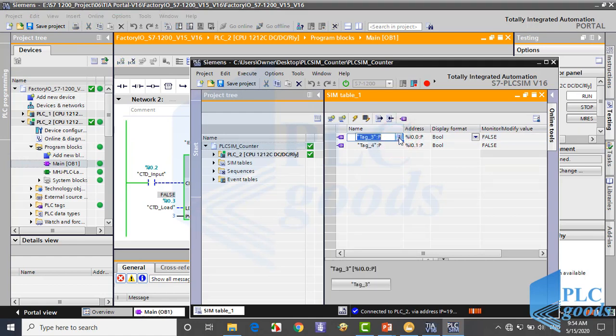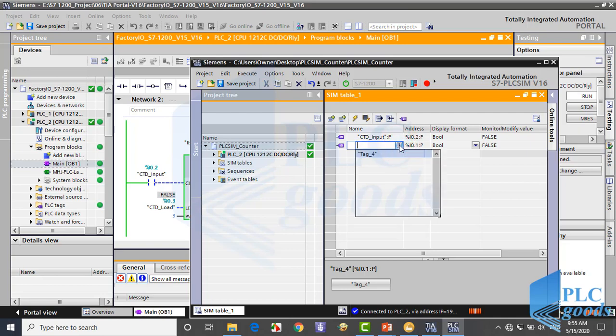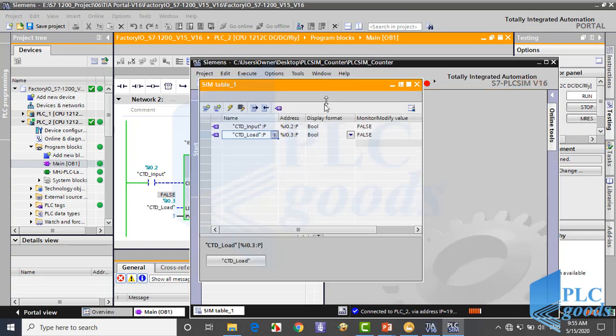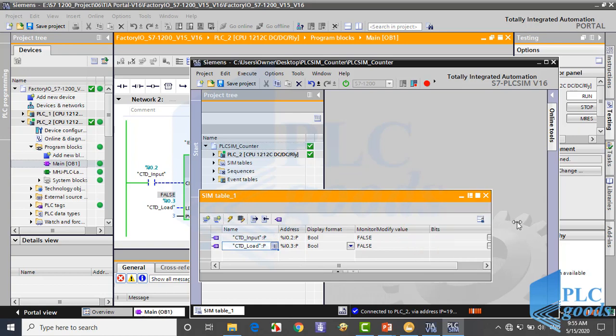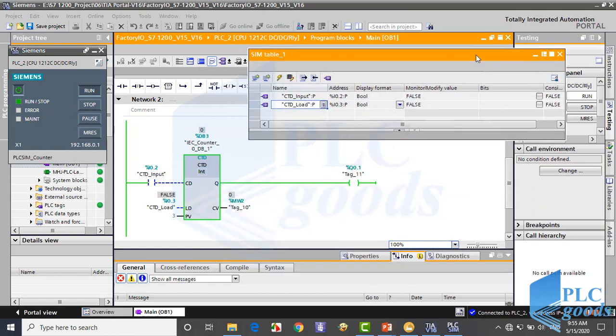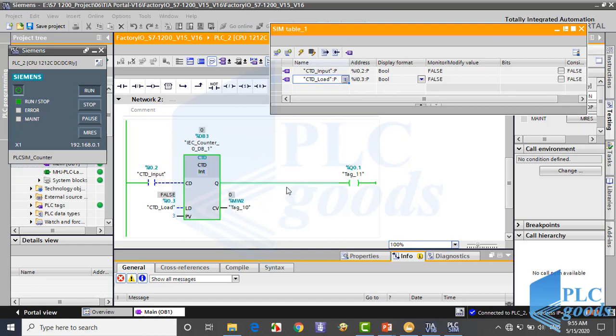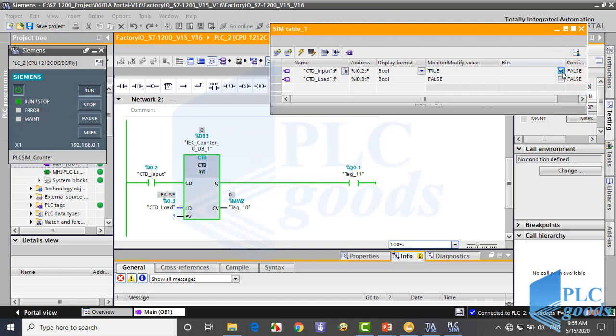Now let me change these inputs. As you see, at the first time this output is on. When the load input is activated, this counter copies the preset value to the counter value. Then with another input, I can decrease the counter value until it reaches zero, which turns on my output. With next pulses, the output will remain on until the next positive pulse at the load input.